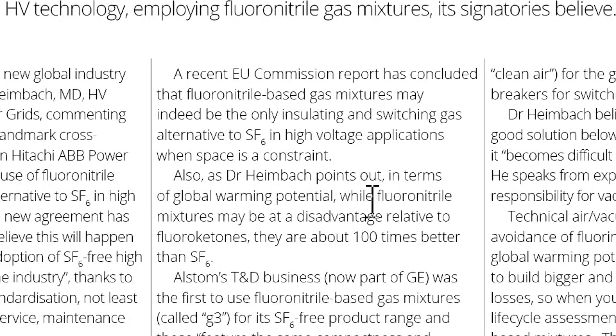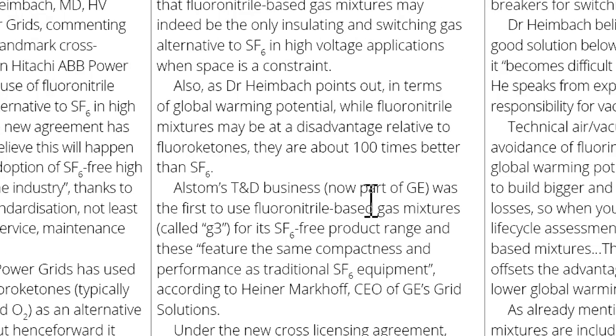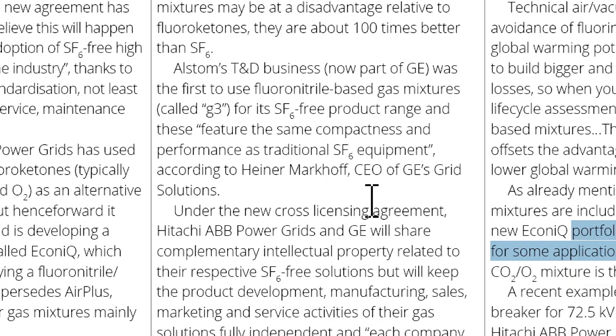A recent EU Commission report has concluded that fluoronitrile-based gas mixtures may indeed be the only insulating and switching gas alternative to SF6 in high voltage applications when space is a constraint. Also, as Dr. Heimbach points out, in terms of global warming potential, while fluoronitrile mixtures may be at a disadvantage relative to fluoroketones, they're about 100 times better than SF6. Alstom's transmission T&D business, now part of GE, was the first to use fluoronitrile-based gas mixtures, called g3, for its SF6-free product range, and these feature the same compactness and performance as traditional SF6 equipment.